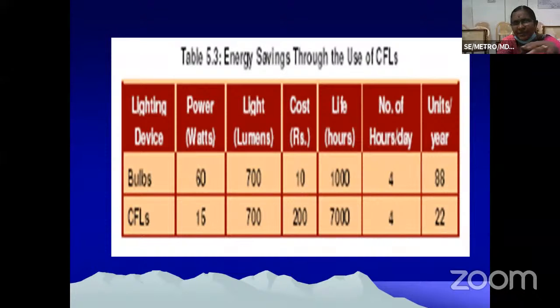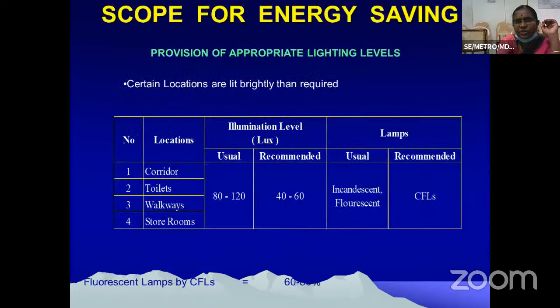This is a comparison between the ordinary incandescent bulb versus the CFL in terms of power, light, cost, life cycle, and number of hours it is used on. Scope for energy saving: provision of appropriate lighting levels. Certain locations are lit more brightly than required. For example, corridors, toilets, walkways, storerooms usually have 80 to 120 lux, whereas recommended is 40 to 60.